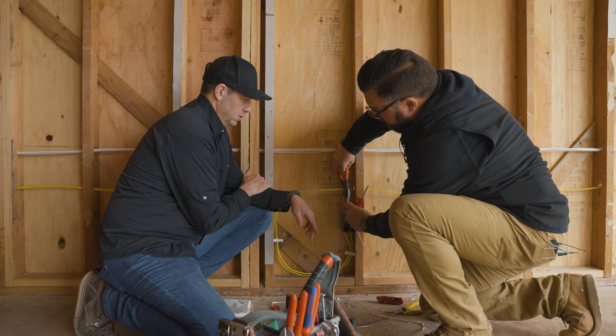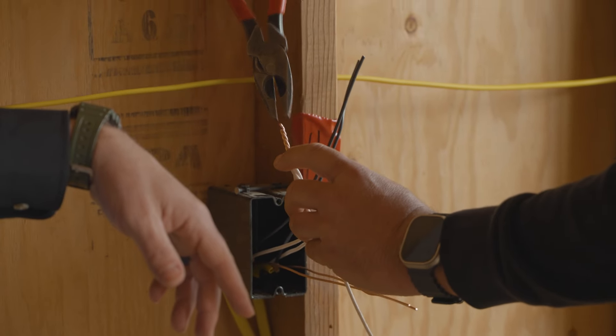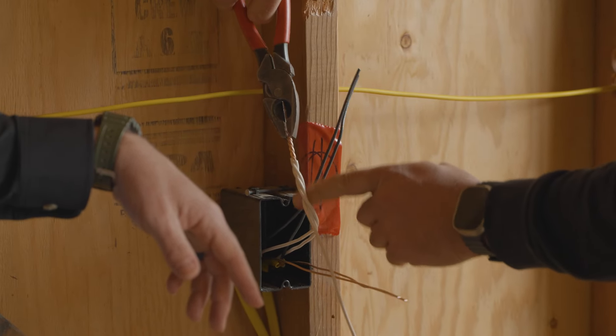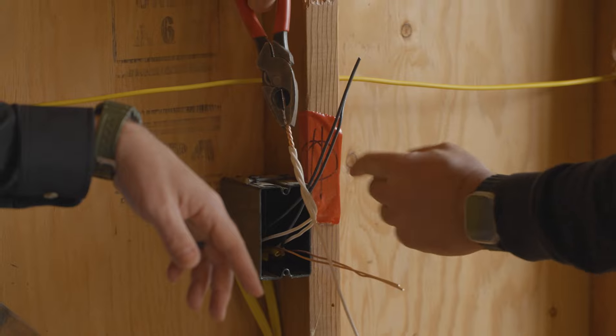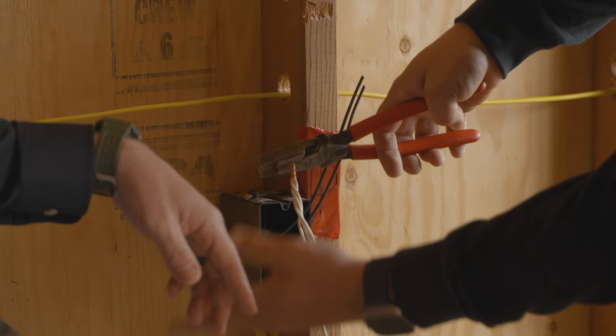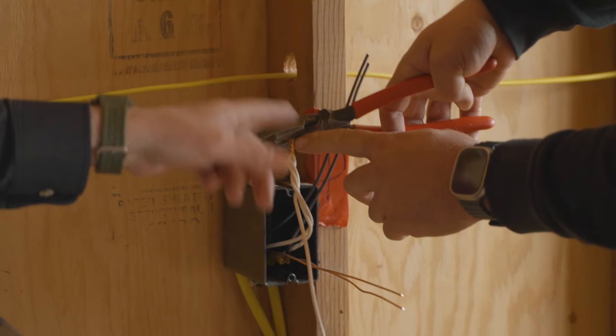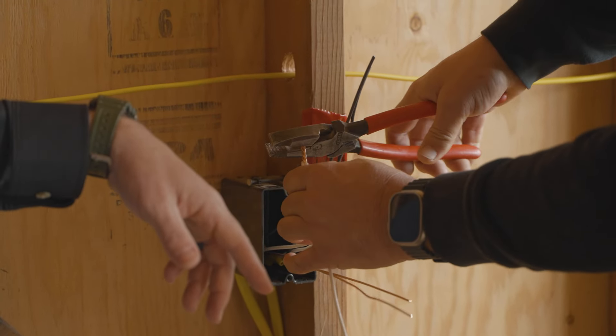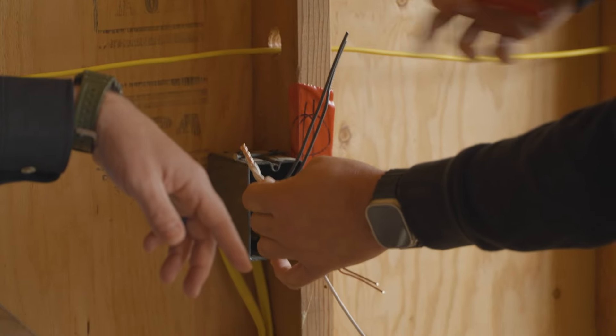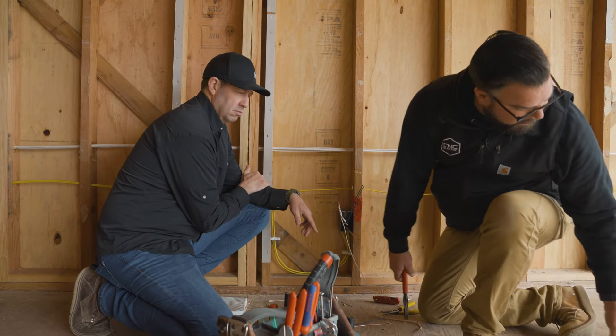This is what we call a pre-twist. It's not required — you'll see a lot of guys just group those together, zip on a wire nut, and they're done. But for most trained and proud electricians, it's a pre-twist. You're tying them together before you even put a wire nut on. My wire nut is really just there to insulate and hold those conductors. That's a solid connection. Nice three to four braids, then trim off the top ugly part. Leave at least three to three-and-a-half braids.